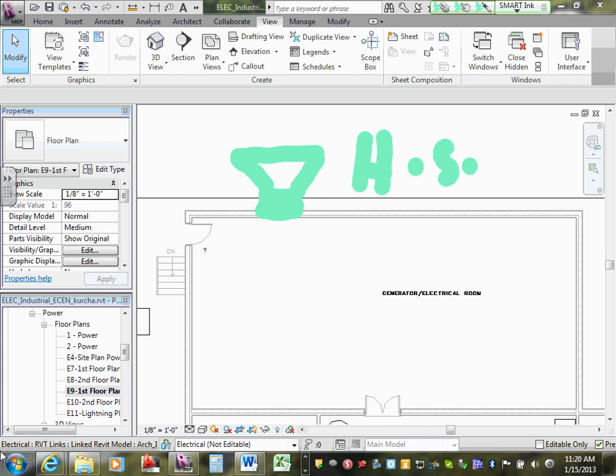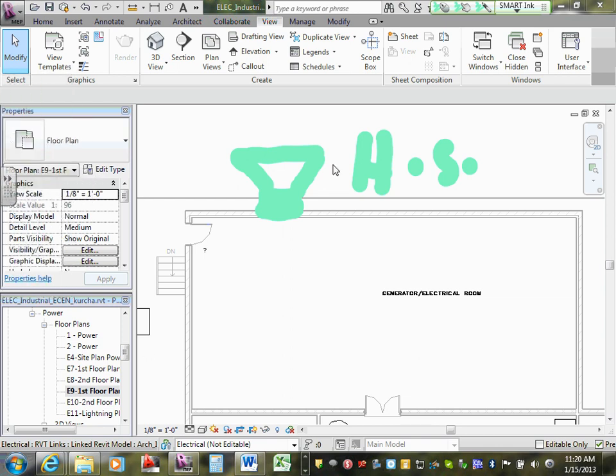Yep. And usually, again, 120 volts, so usually we don't touch it. They'll just run it straight through where the horn strobe is located. It's gonna be located right above the Siamese connection, and they're gonna run that straight into where the riser is to the main flow. So all it does is it goes off, tells the fire department, hey, here's where you need to connect.